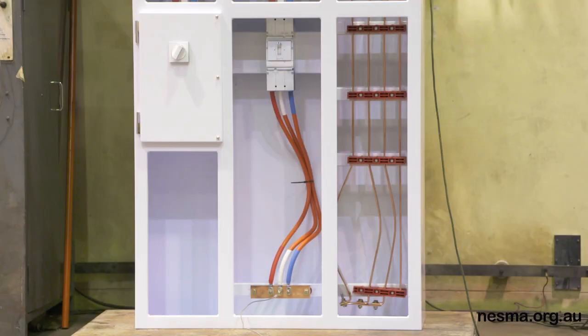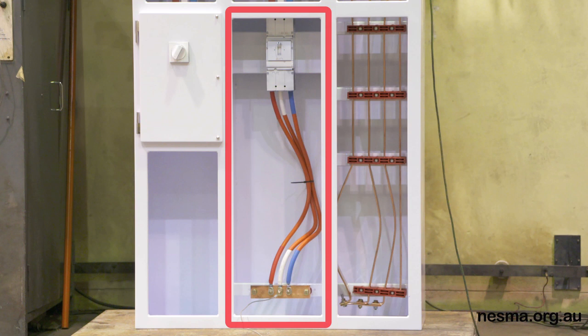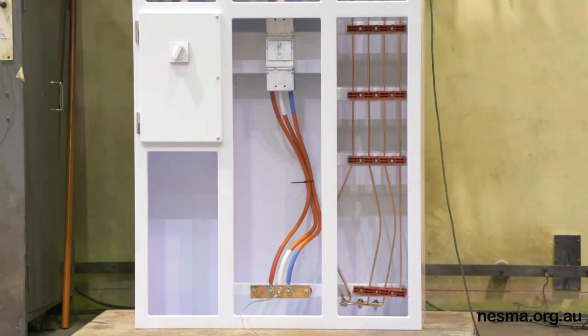Okay, now to the test in the middle tier. What we have is a circuit breaker of unknown manufacturer origin. Even though I think someone might be claiming that it's their breaker now because it did everything it was supposed to do. What we have is some cables going out on the load side terminals, and we might just play through a slow-mo of the test because there's a lot of arc product given out through the circuit breaker when it's operating. This is the same 50 kA fault level. We're just seeing the walls flash backwards and forwards. So that's all the stuff you missed because you blinked.